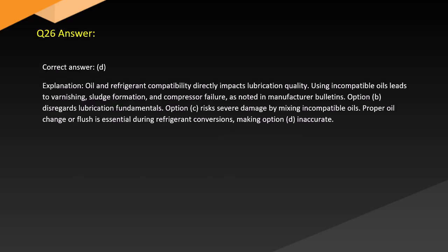Answer. Correct answer. D. Explanation. Oil and refrigerant compatibility directly impacts lubrication quality. Using incompatible oils leads to varnishing, sludge formation, and compressor failure as noted in manufacturer bulletins. Option B disregards lubrication fundamentals. Option C risks severe damage by mixing incompatible oils. Proper oil change or flush is essential during refrigerant conversions, making option D inaccurate.